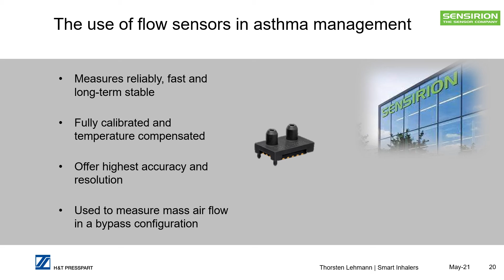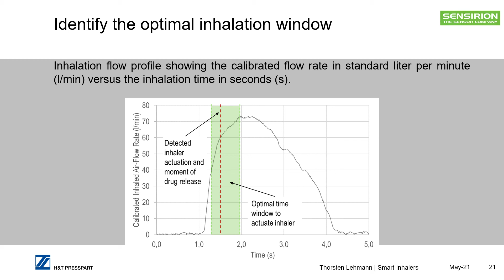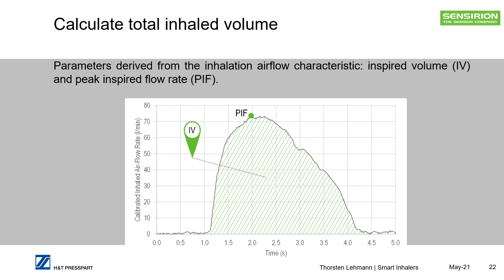Here we see the inhalation profile of a patient over time. The optimal inhalation window can be identified on the curve showing shortly before the peak inspiratory flow rate and is highlighted here in green. Furthermore, inhaler actuation and the moment of the drug release can be detected. This moment can be compared to the optimal actuation window to conclude whether the actuation was performed correctly. The inhalation profile gives us an indication whether the patient inhaled deep and slow enough. The flow sensor can identify the peak inspiratory flow rate. The integration of the flow rate over time would give us then the total inspired volume IV.